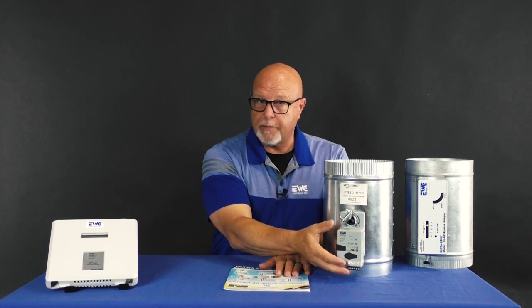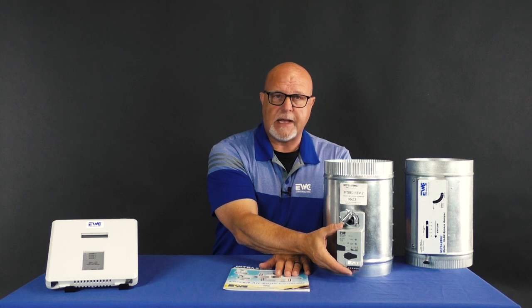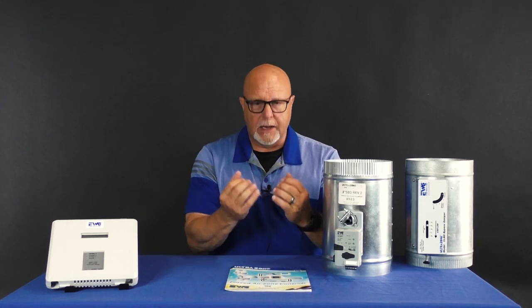It will go through a step where it will go to the close side and hold there for approximately 10 seconds. It will then capture that static pressure and put it into its built-in memory bank. Even through a power failure, that is a static number. It will not ever lose that. When it gets done with that, it will automatically rotate to the open side. Again, it will hold there for approximately 10 seconds and capture a static pressure, again putting it in the memory bank.